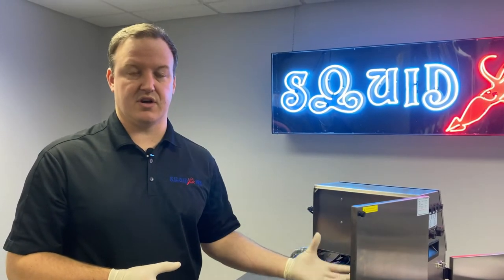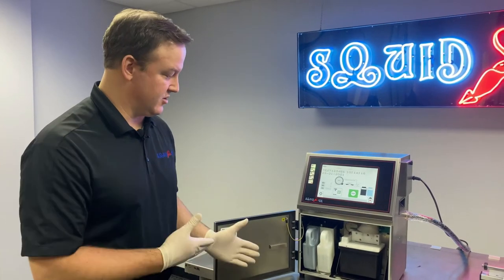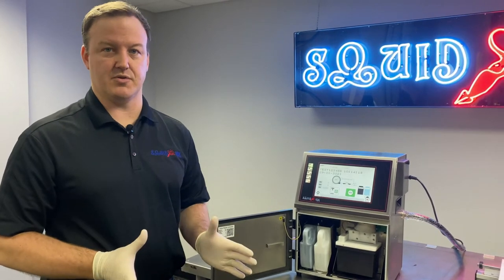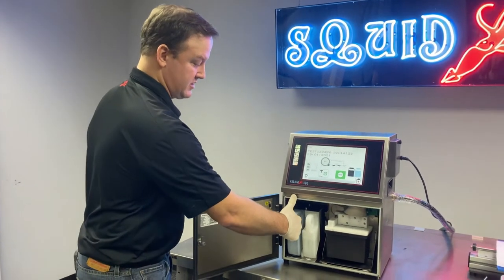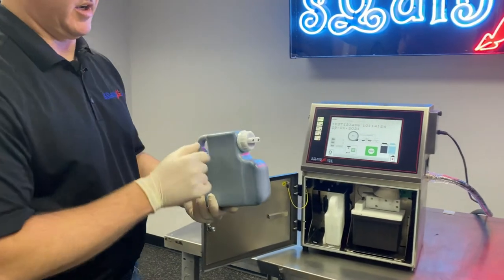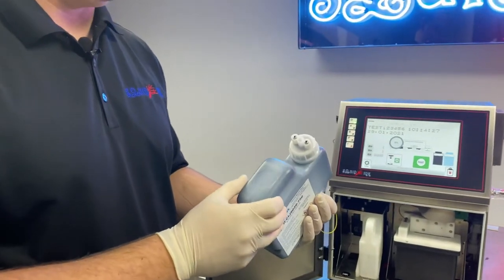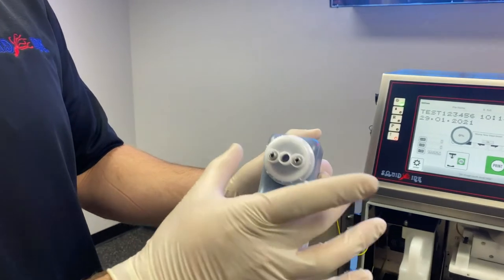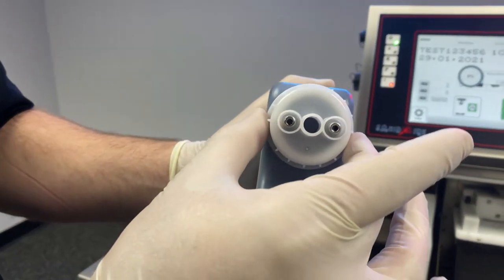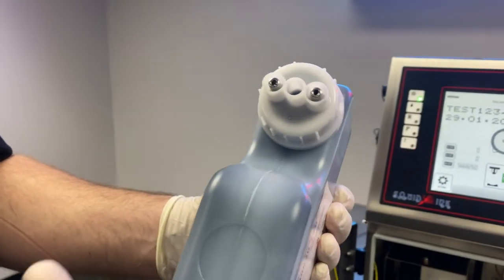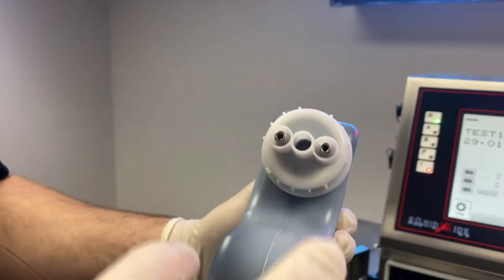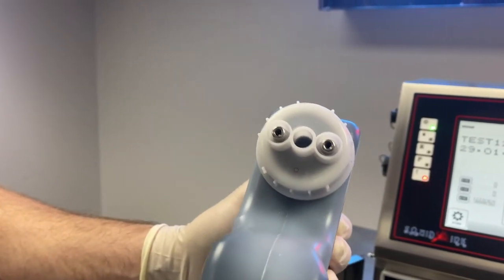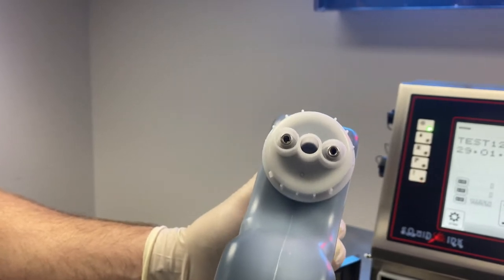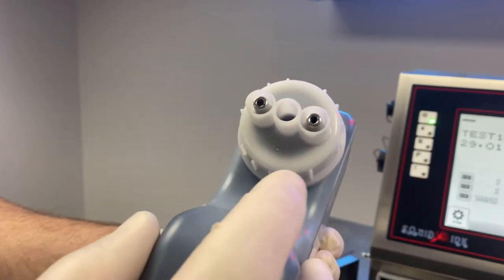So we're going to take a look at the cartridge first and just make sure everything's okay there. I'm going to slide the cartridge out, the ink cartridge, and we're going to look at a couple of visual indicators here really quick. One is we're going to make sure that the cap is on correctly, that someone didn't try to take this off or put it on backwards, whatever it might be. If that were to happen, if the cap were on backwards, the draw tube would be on the wrong side, and instead of pulling ink out, we'd actually be blowing air into the cartridge.